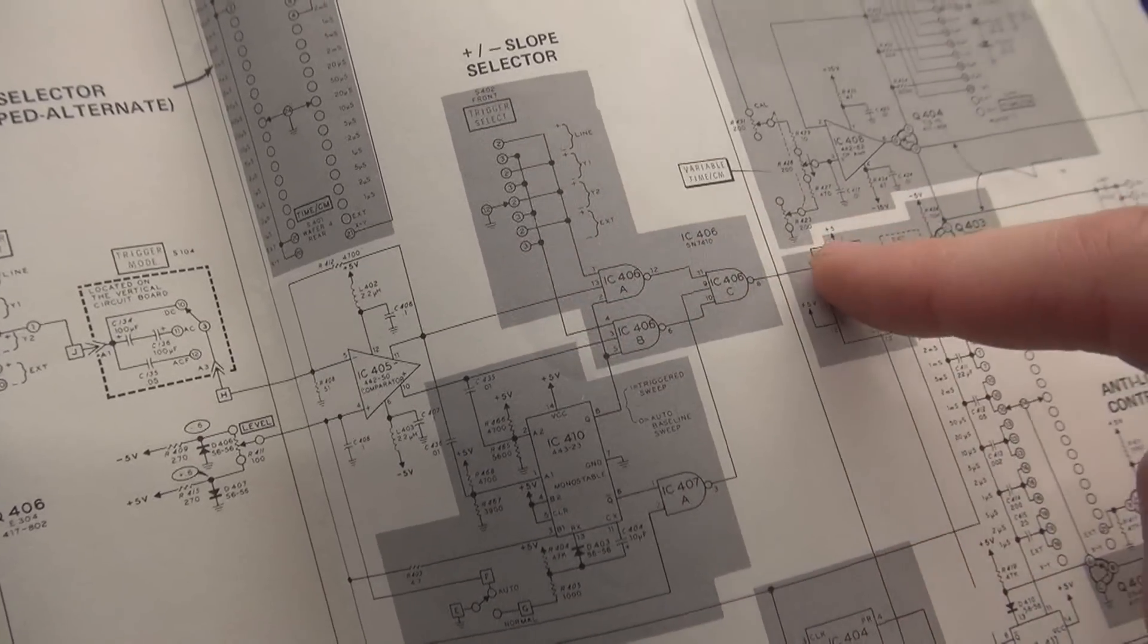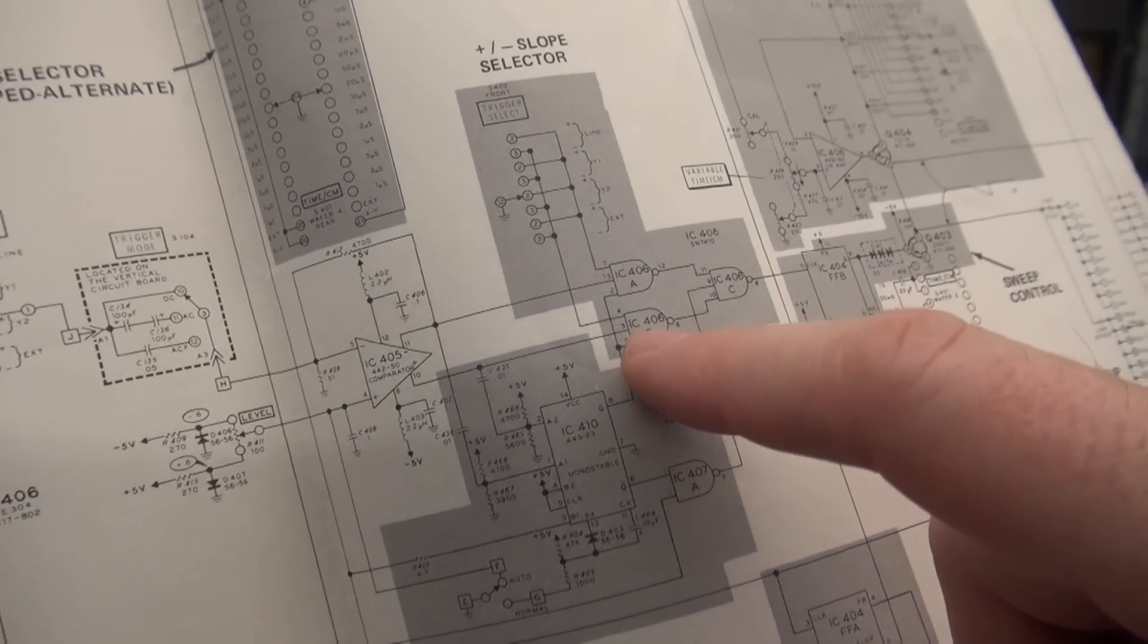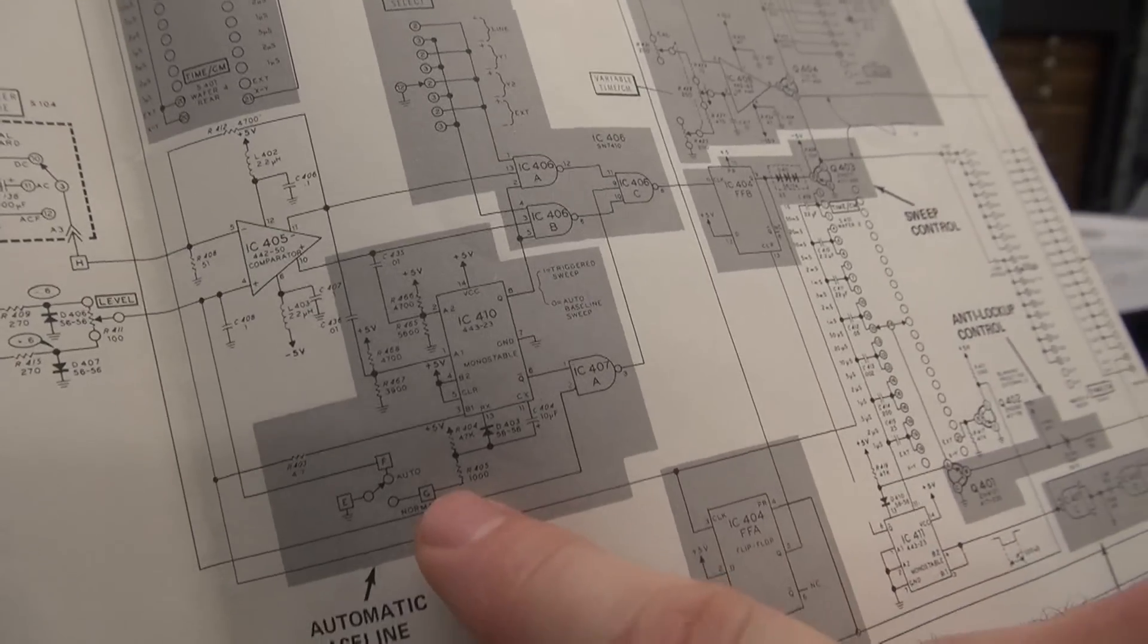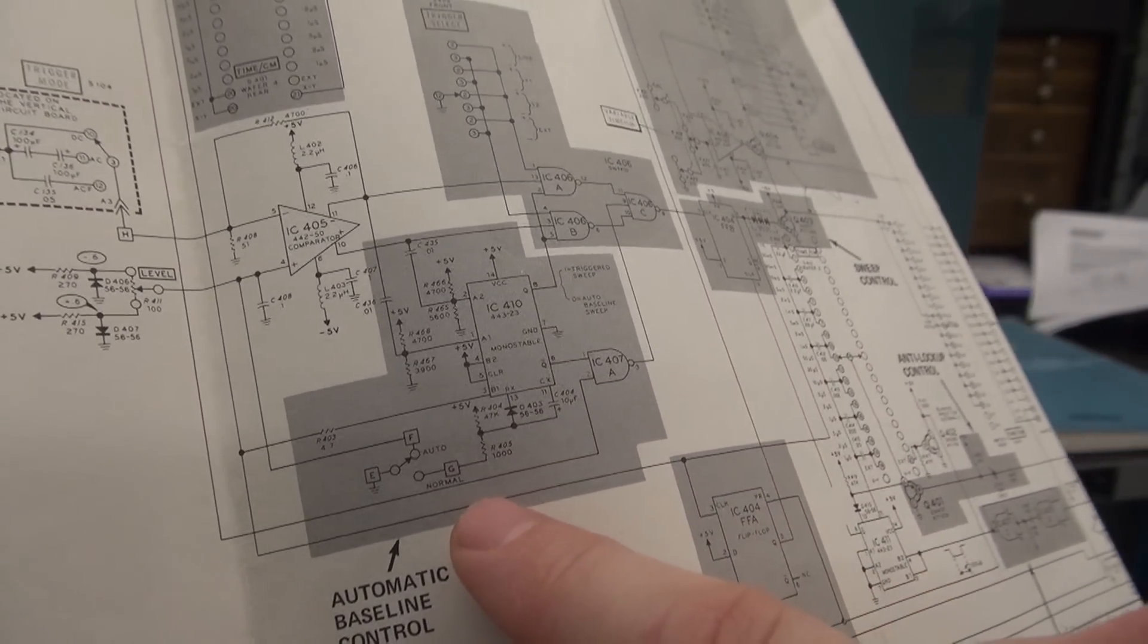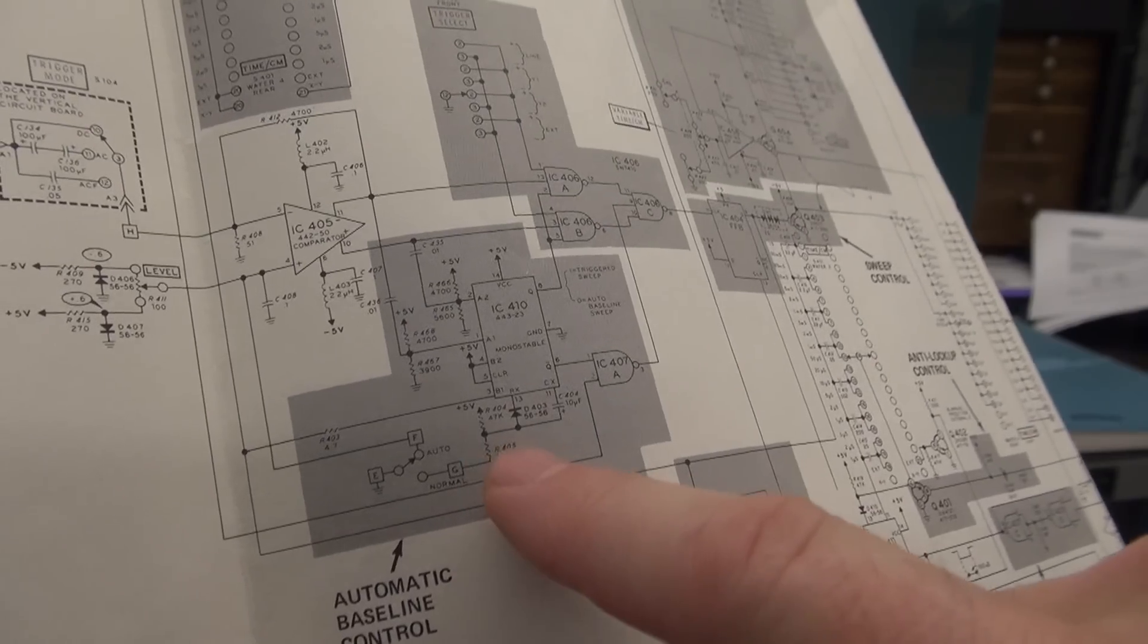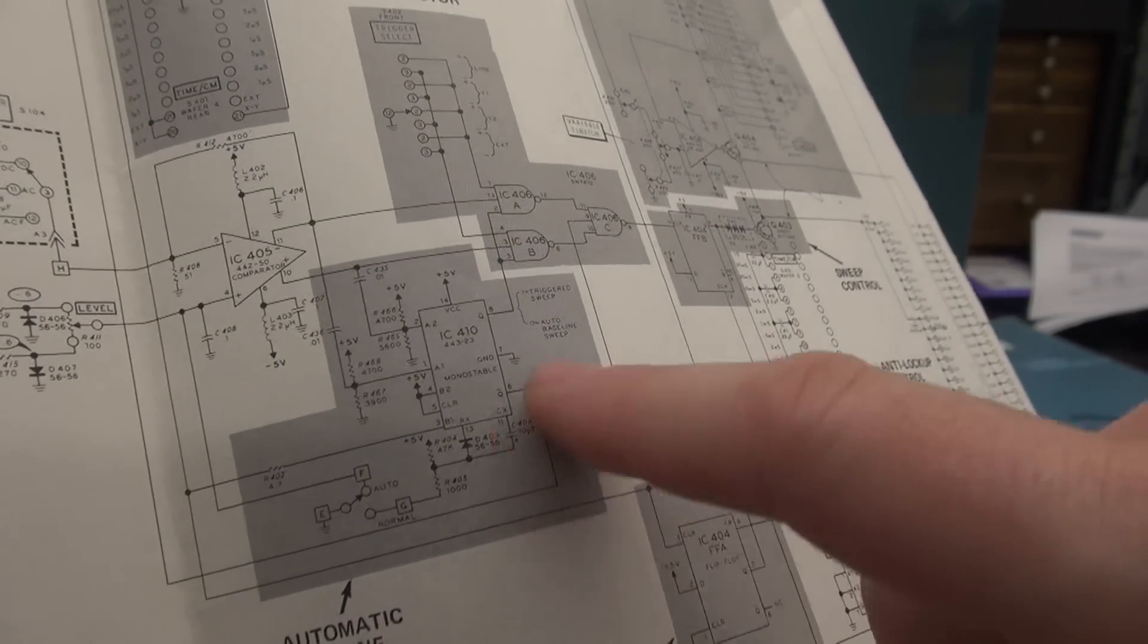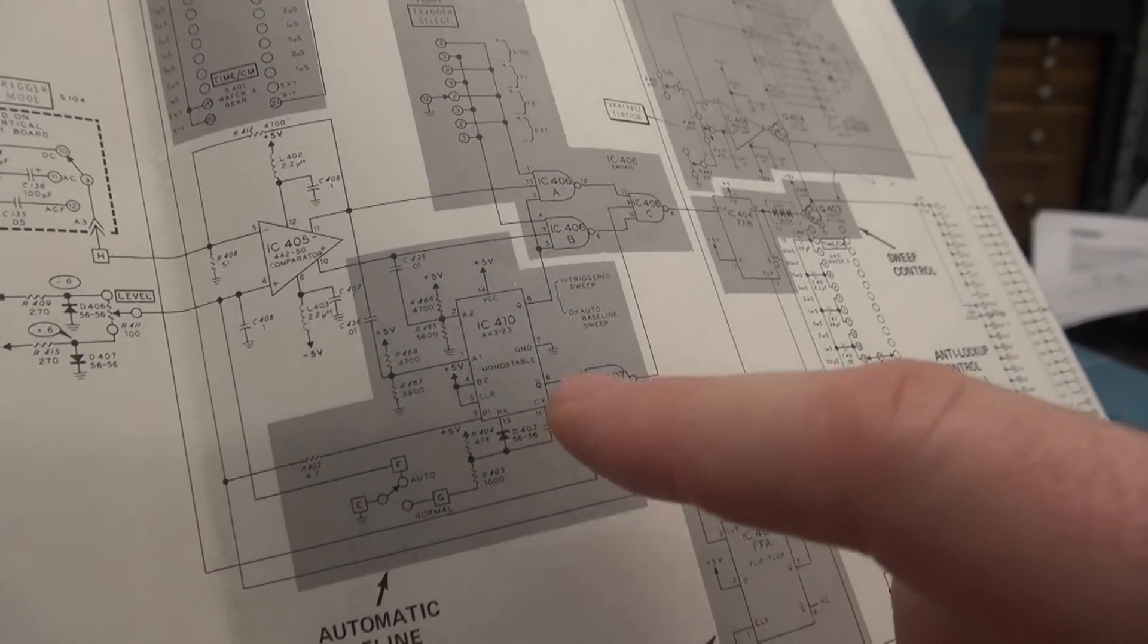So that is not working. It's not getting that signal. Something's interrupting it. And then if you look closer, you can see the auto and normal trigger switch. So when you go to auto, it actually bypasses IC405. These other chips do stuff and make it auto lock, and that's not quite working right either.